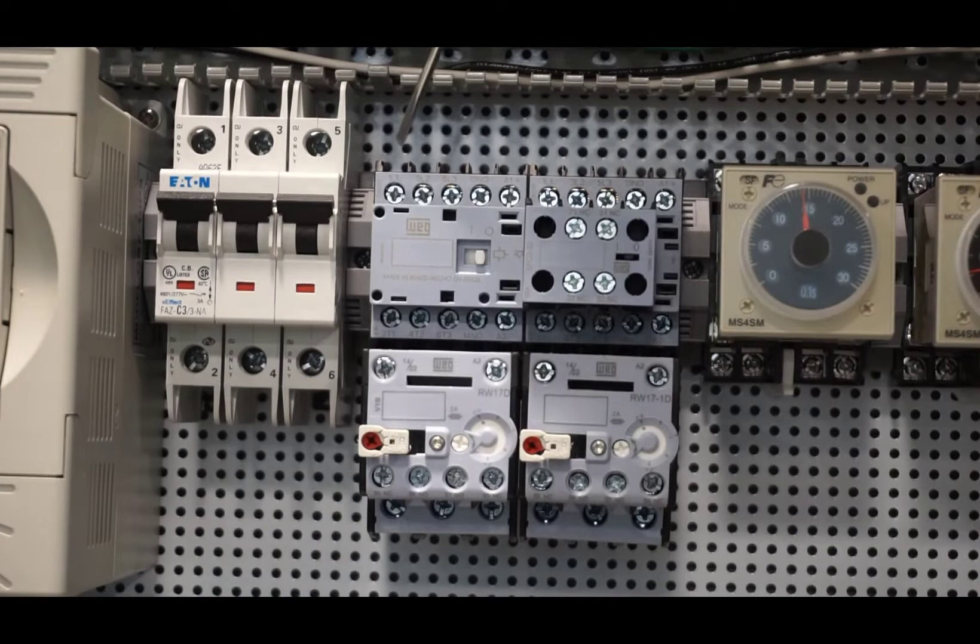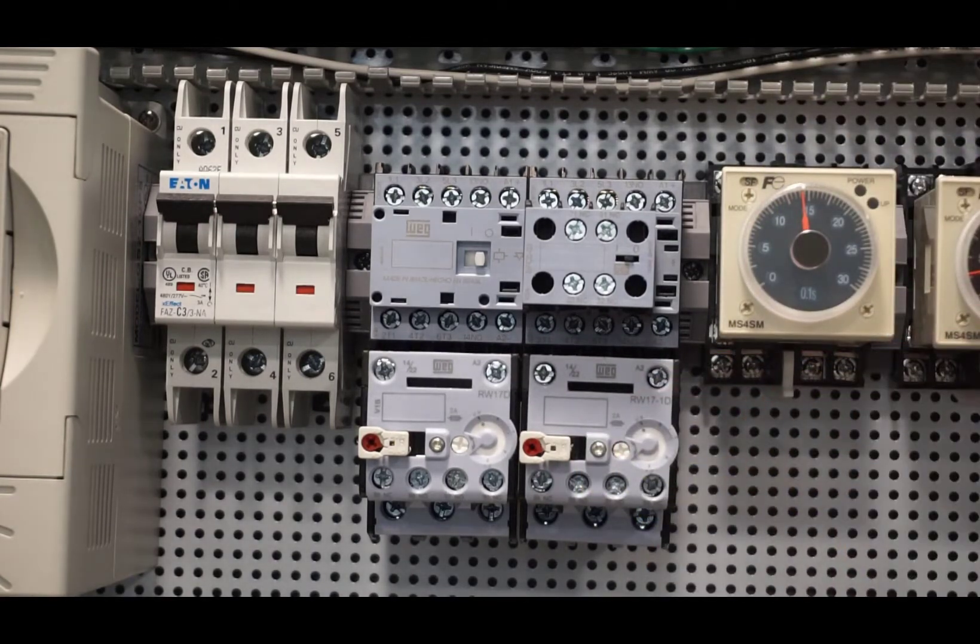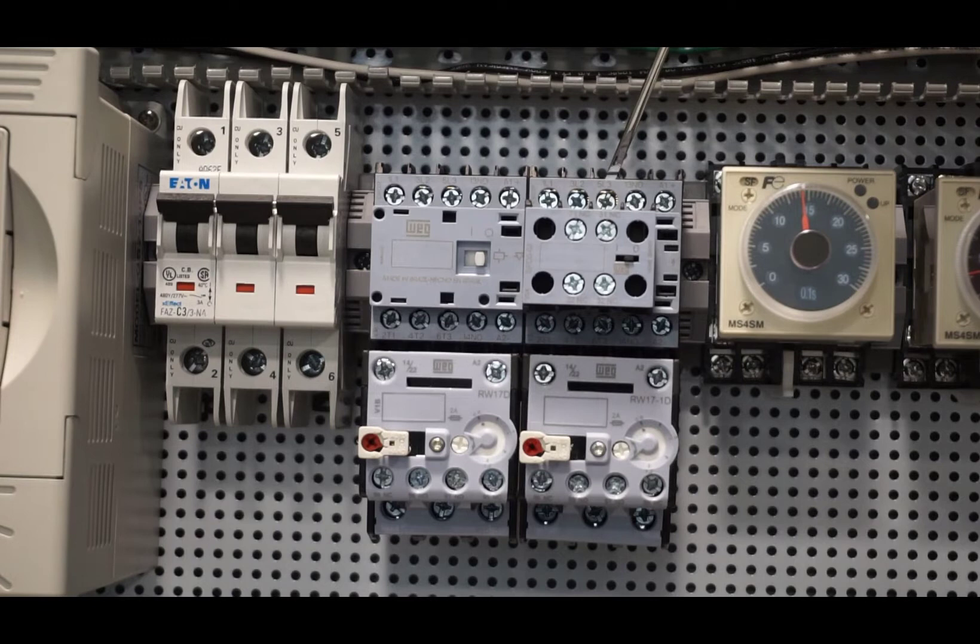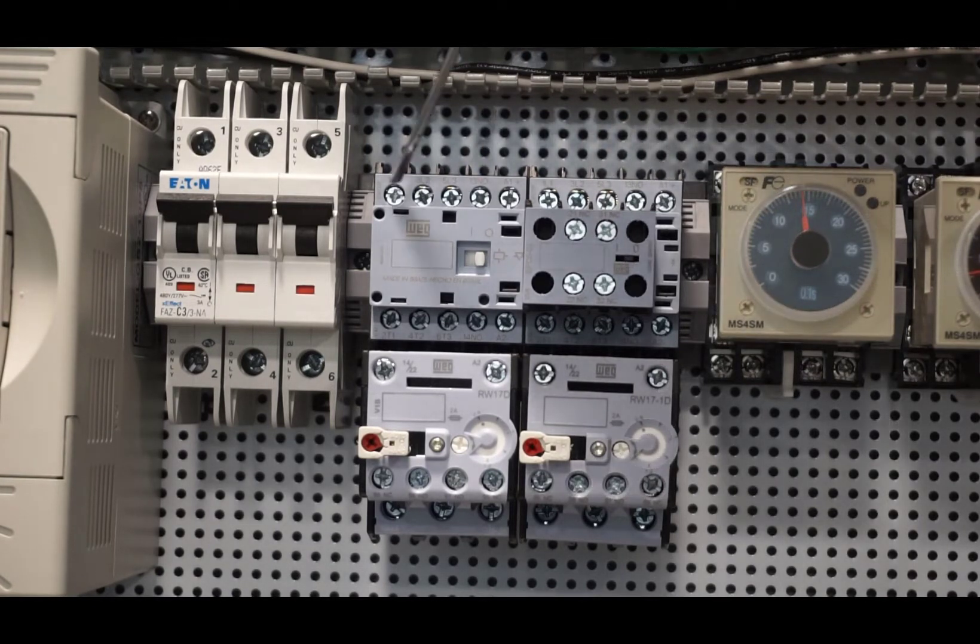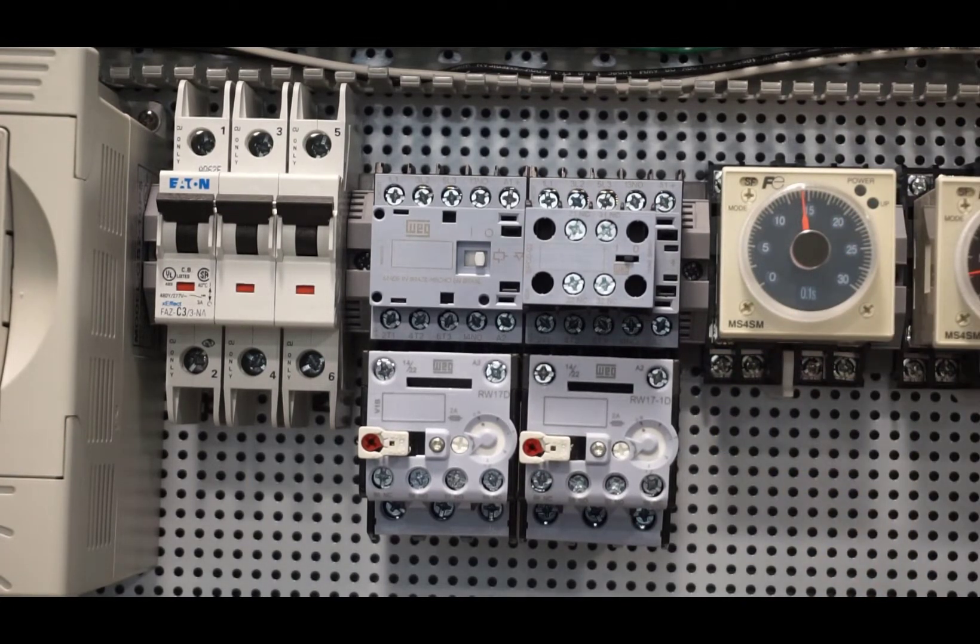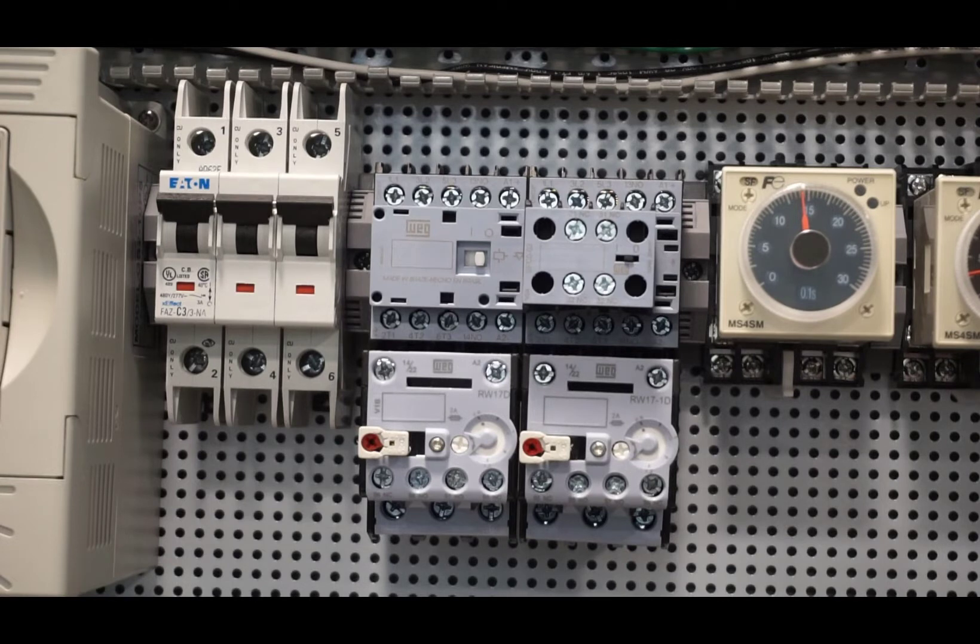The reversing starter is made up of two contactors, mechanical interlock, auxiliary contacts, and two overload relays. There's the auxiliary contact block, the mechanical interlock, and the overload relay. One set of contactor and overload relay makes up a starter.